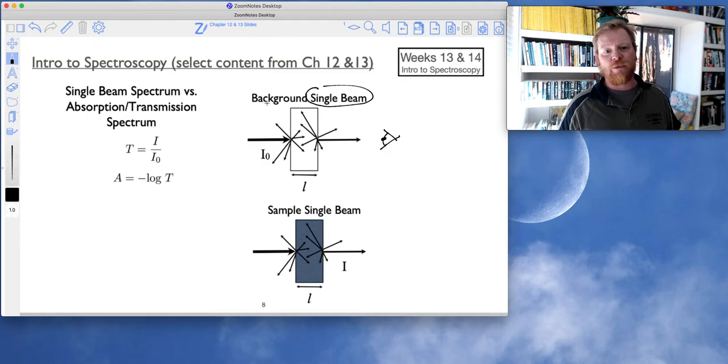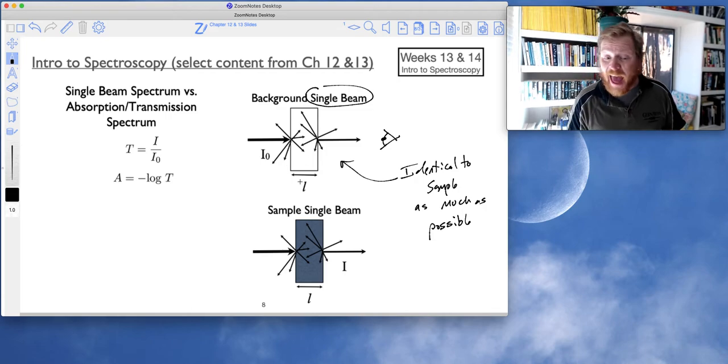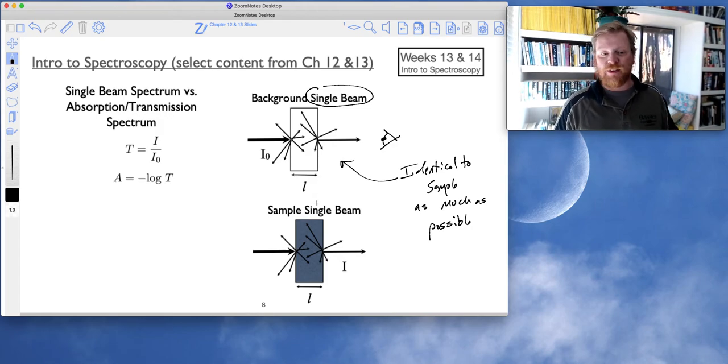So the way we get around with that is we first record a background. So this will be identical to the sample as much as possible. So typically, if we can, we would want to use the same cuvette. If we can't use the same cuvette because we want to keep running multiple samples, then at the very least, we would do some type of study to figure out how different each cuvette is from the next. If there's little bad spots in the glass that contribute to scattering, we would want to maybe throw one of those cuvettes out and use a more pristine one.